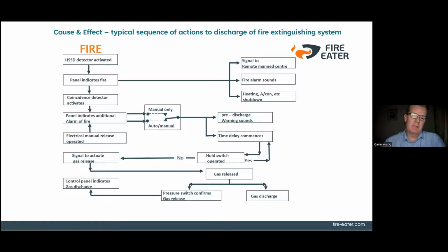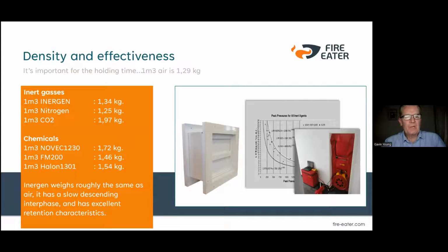Once that countdown has elapsed, there's a signal. 24 volts goes down the solenoid circuit, activates the solenoid, and discharges the gas into the room. At that point, the pressure switch will give a gas gone or gas release signal back to the panel, and the gas basically then stays in the room for a minimum of 10 minutes. So it's important to look at the density of the type of gas that you're looking at. 1 cubic meter of air is 1.29 kilograms. You need, as I said, to have that gas within the room for 10 minutes.